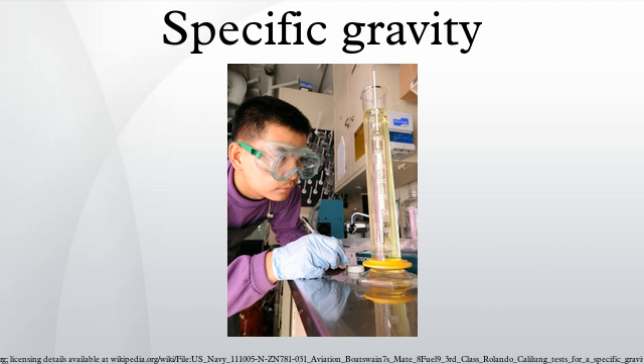The submersible probe head contains a mathematically characterized spring float system. When the head is immersed vertically in the liquid, the float moves vertically and the position of the float controls the position of a permanent magnet whose displacement is sensed by a concentric array of Hall effect linear displacement sensors. The output signals of the sensors are mixed in a dedicated electronics module that provides an output voltage whose magnitude is a direct linear measure of the quantity to be measured.